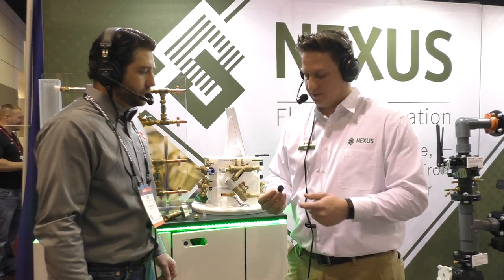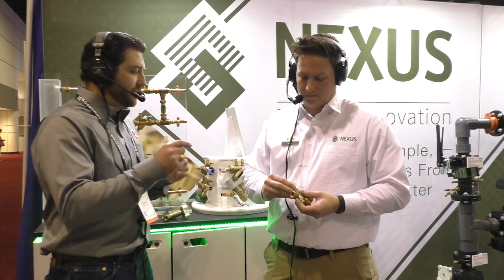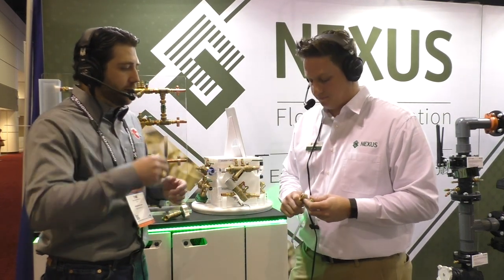But the main difference between this valve and what you would see as the Ultramatic, everything's going to work the same internally, but you're going to have a composite cartridge, and so you still have the stainless steel moving parts, but the housing is going to be composite as opposed to brass. Sure, so to meet the low lead standard. Right. This is a great way to automatically balance for those different branch zones. Don't have to measure your DP and manually set the valve. It's going to automatically balance that flow.